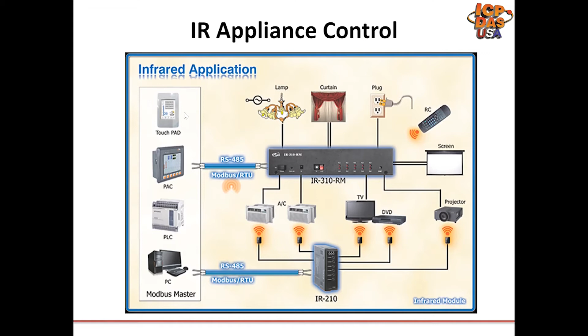Now, I keep referring to these as IR controllers, but they're not actually the controllers, these are what send the IR commands. What you send the actual commands with, on the other end of your serial or Ethernet line, can be a touchpad, a PLC, a PC, or an industrial PC. You program and control the IR modules with a piece of software we call IR Utility, where you configure the different IR channels and associate IR commands with Modbus commands.